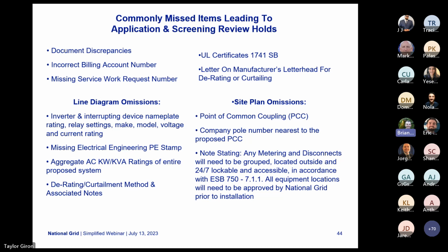In regards to one-line diagrams, some issues we commonly see include inverter and interrupting device nameplate rating, relay settings, make, model, voltage, and current rating missing. As mentioned during the expedited portion, we also see missing electrical engineering PE stamp, aggregate AC kilowatt or kVA ratings of the entire proposed system, de-rating, and curtailment method and associated notes.